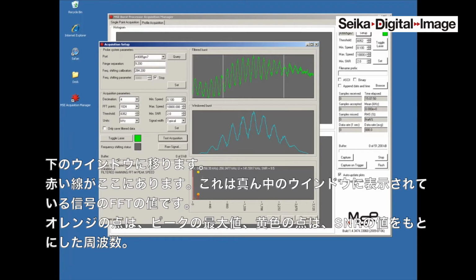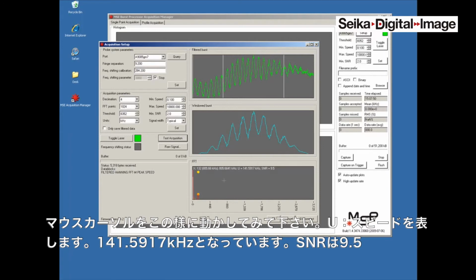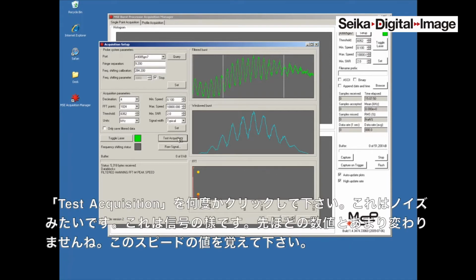based on the value of this SNR. Once you put your cursor on the bottom line, you will see the value of the U, or the velocity for this particle, was 141 kilohertz. And then the SNR is 9.5. You can do a number of test acquisitions just to make sure: this looks like noise, this looks like a signal. And again, the numbers are not too far off, 156.